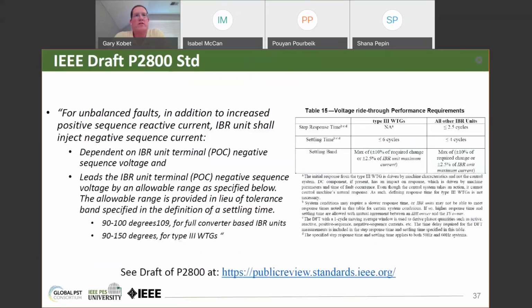And so in the next slide, we have a piece of the draft of the P2800 standard that Puyon mentioned. As he said, the document is available for public review. In a section of that document, one of the requirements is that for unbalanced faults, in addition to positive sequence current, the IBR shall inject negative sequence current with these characteristics: that it be dependent on the negative sequence voltage and also lead the negative sequence voltage by the phase angles shown. I left a footnote down there. It should say 90 to 100 degrees for full inverter-based IBR. There's a footnote 109. I forgot to take out the 109. I apologize for that. But there is a requirement for IBR to produce this negative sequence current such that the relays that are out there now will be able to actually tell whether there's a fault and determine fault direction.